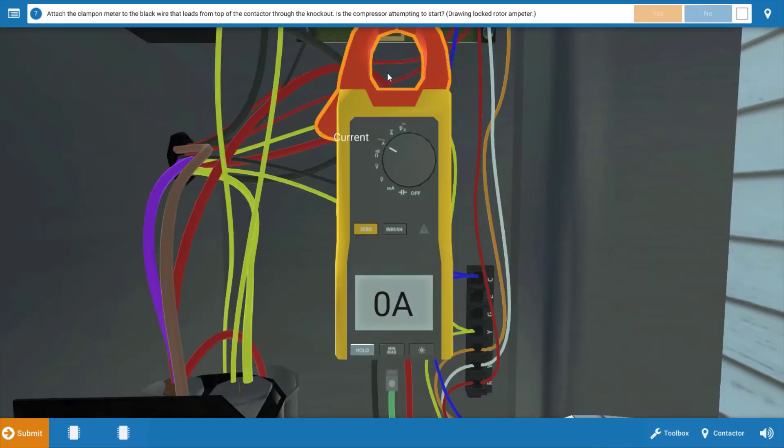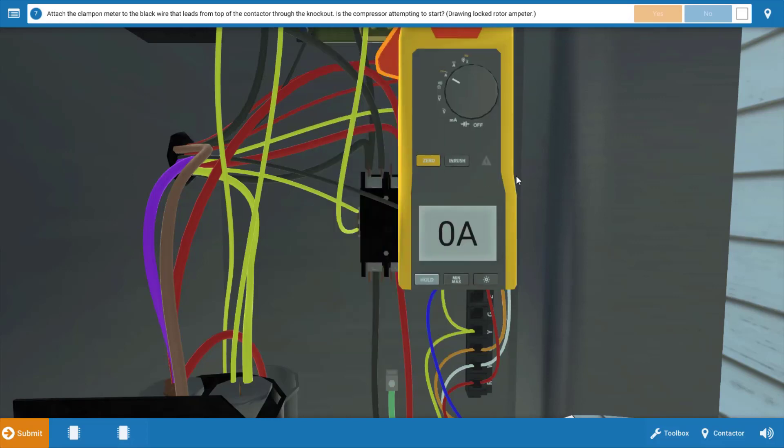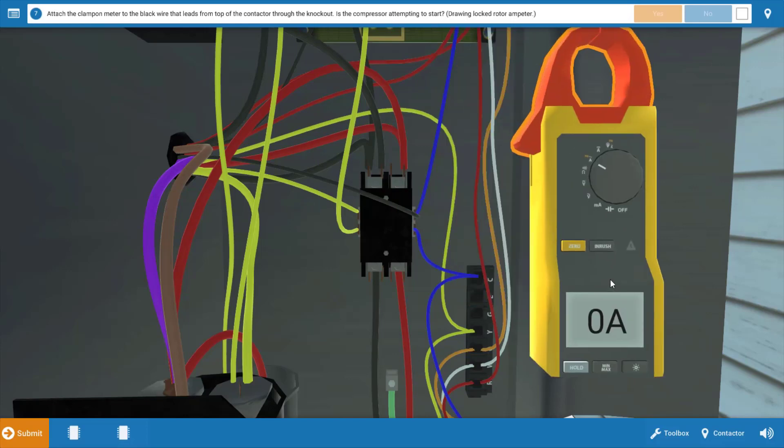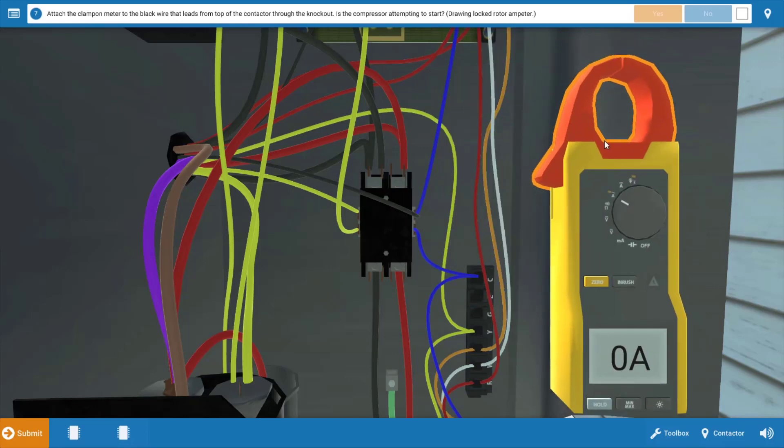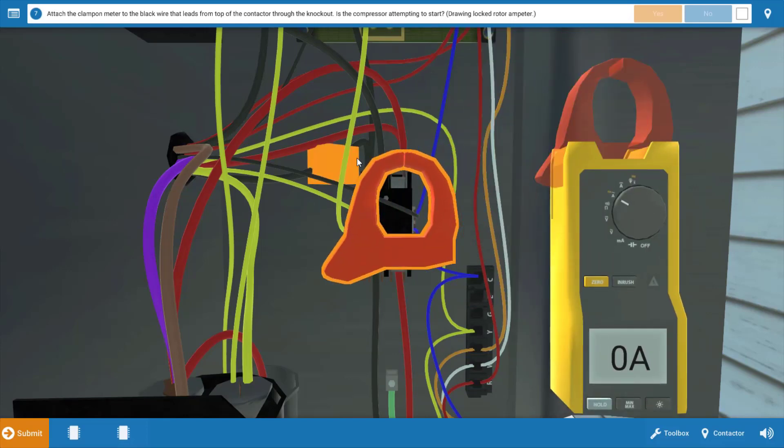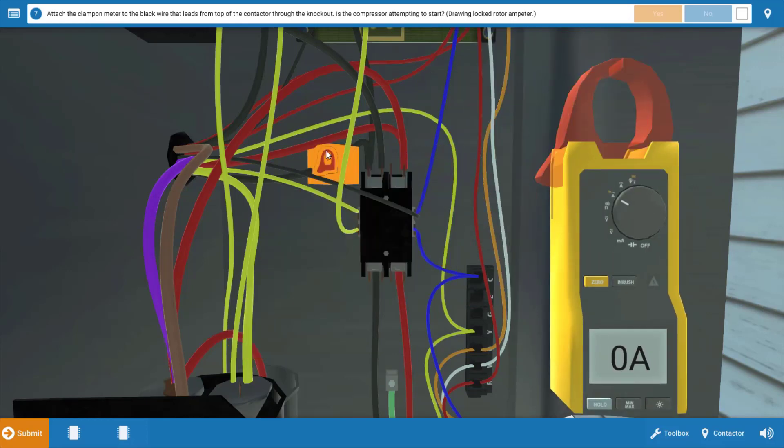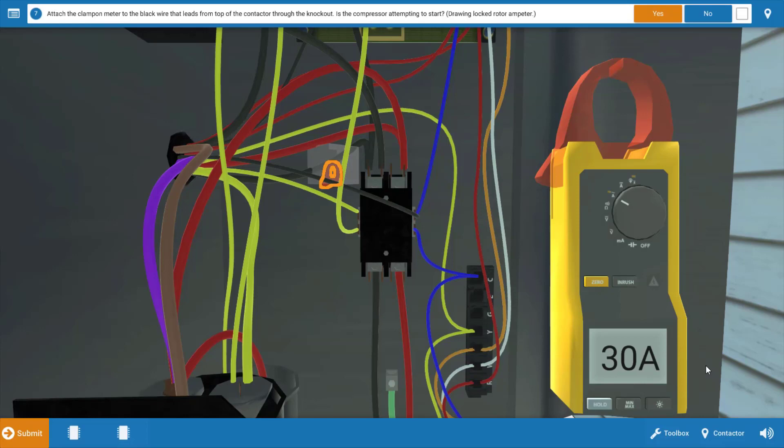And our next step is to measure current of the compressor, and this is going to verify if the compressor is actually running, whether it's off or whether possibly it's cycling on and off. So we're going to take the jaws of our clamp-on ammeter, and we're just going to clip them around the common wire from the compressor. That's this black wire. And we're going to watch the amperage on the meter for just a second. And if we take a look, we can see we've got zero amps, but then it goes to 30 amps for just a brief second and then shuts off again.